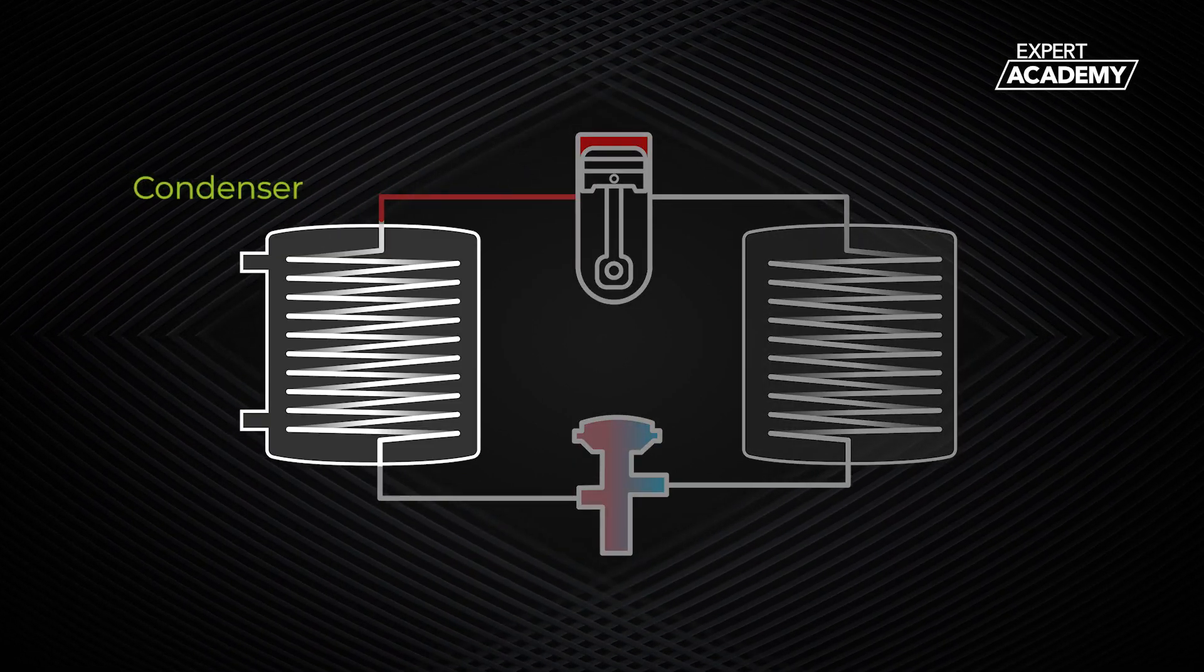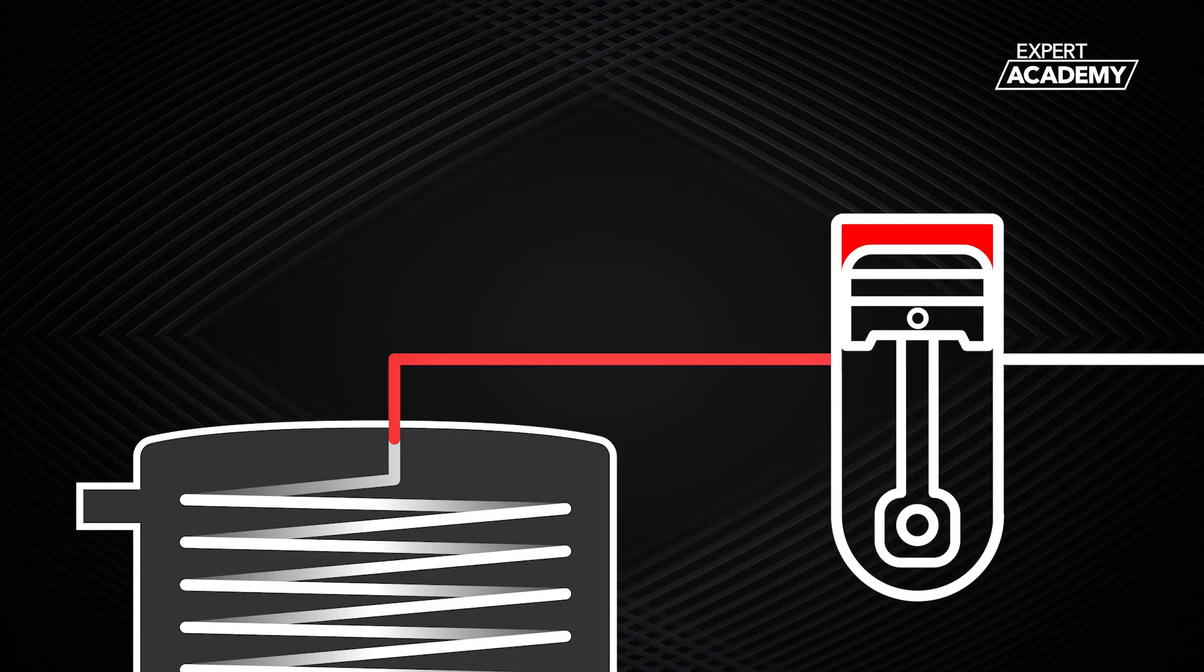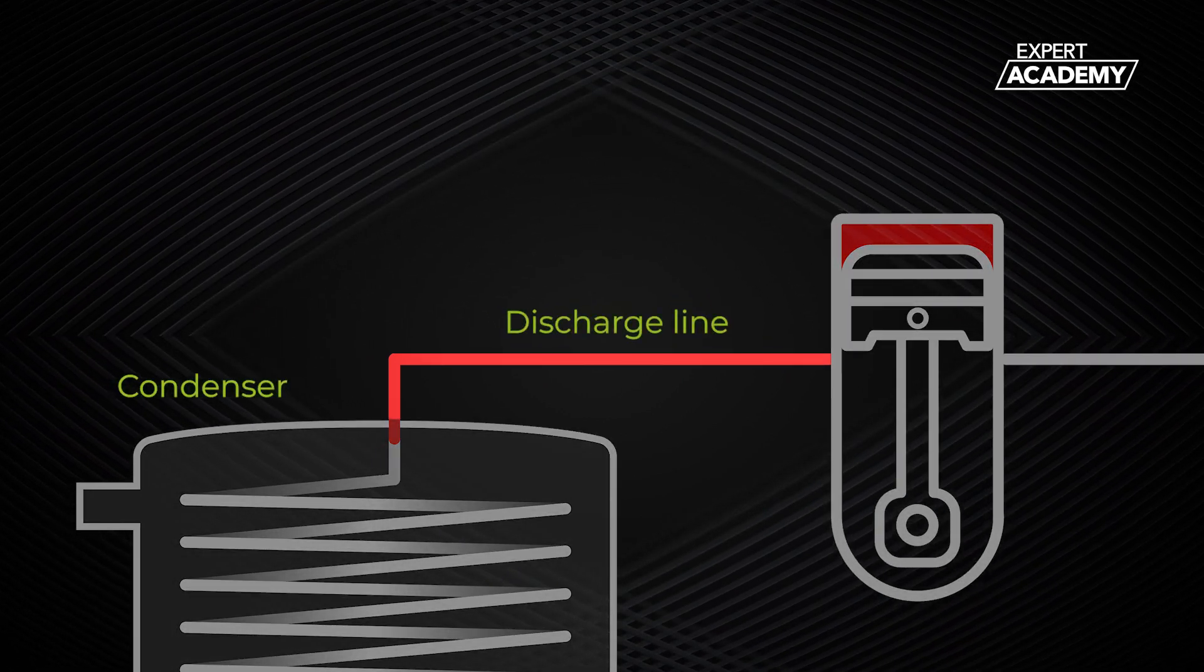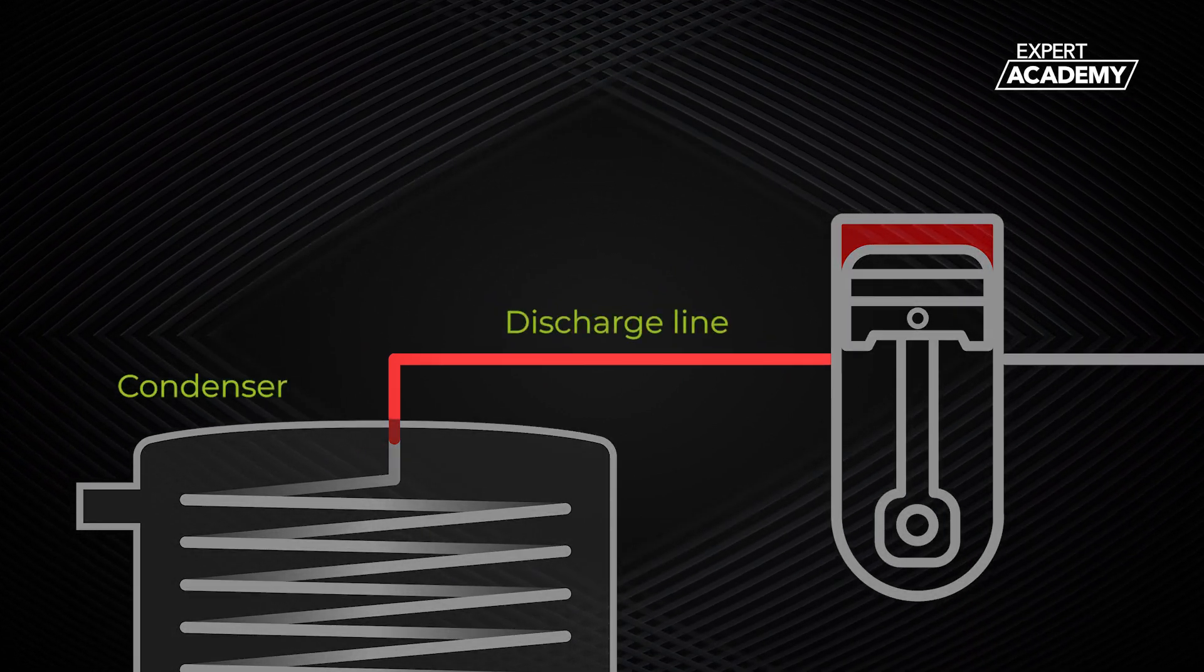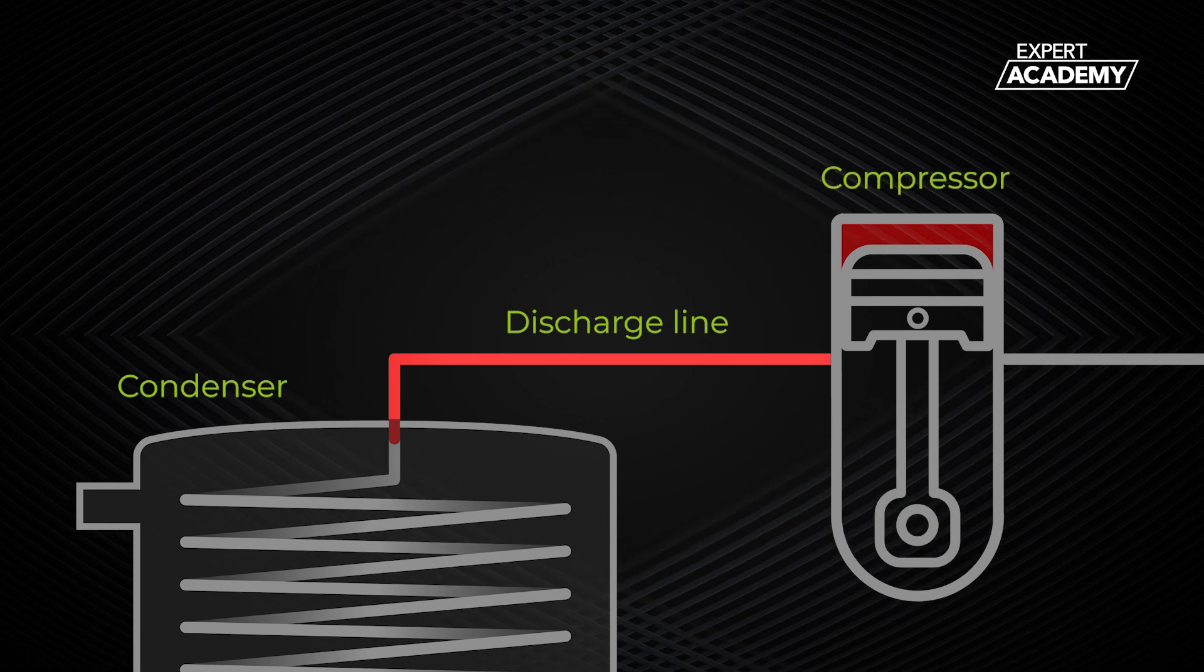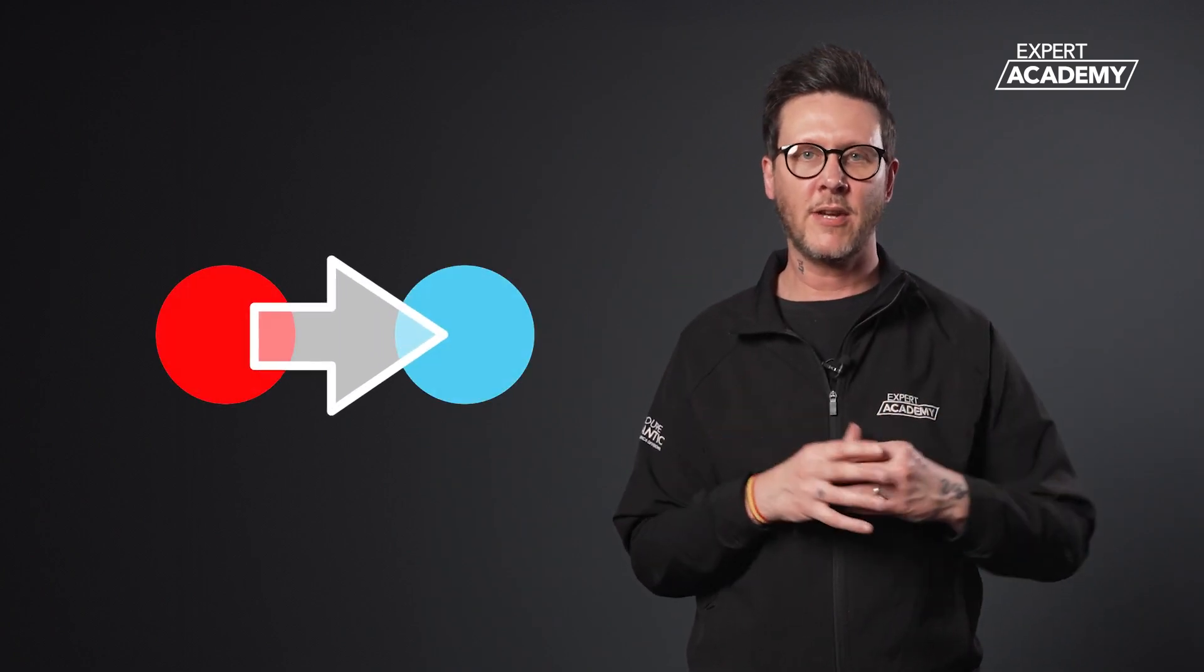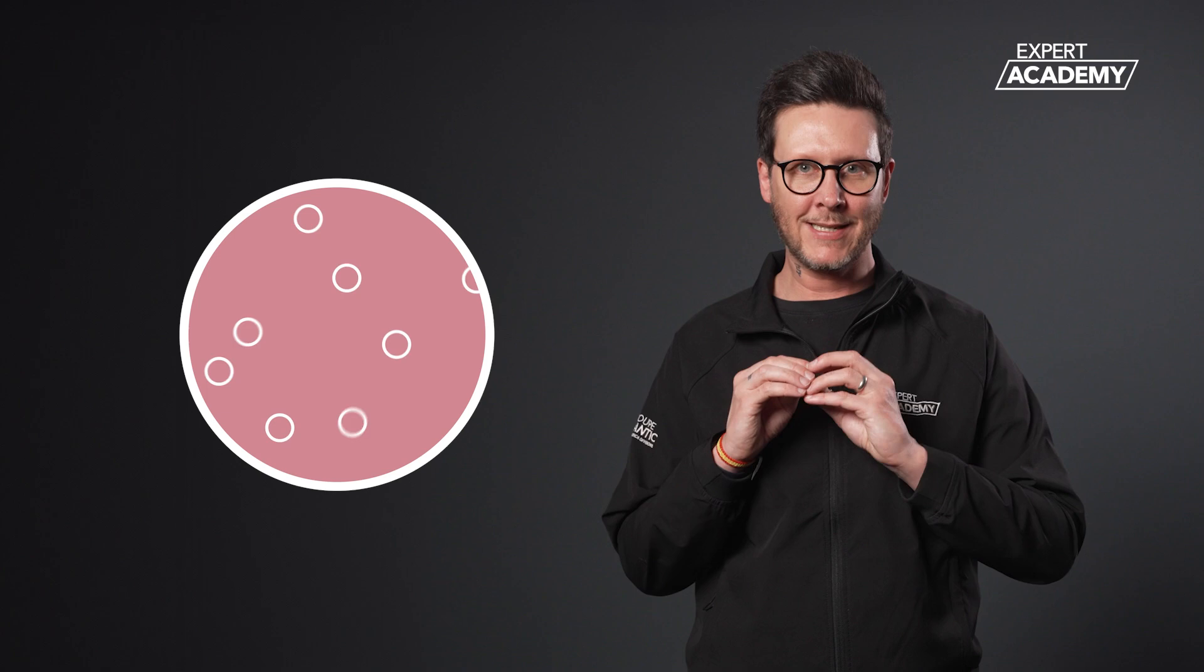The next stage is the condenser. The high pressure, high temperature vapor enters the condenser via the discharge line. The discharge line connects the compressor to the condenser. Remembering that heat moves from areas of higher temperature to areas of lower temperature. The greater the difference, the bigger the transfer. And when we cool a vapor down it condenses, changing state from a gas to a liquid, releasing or rejecting the heat energy it has absorbed.